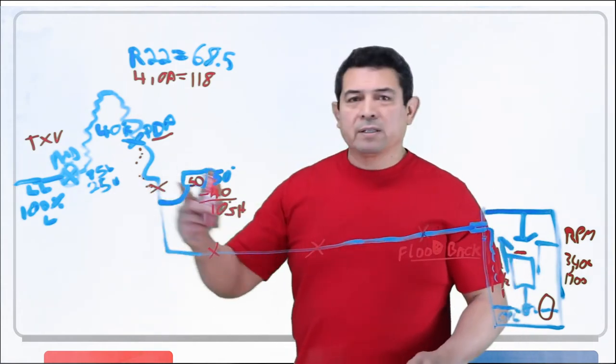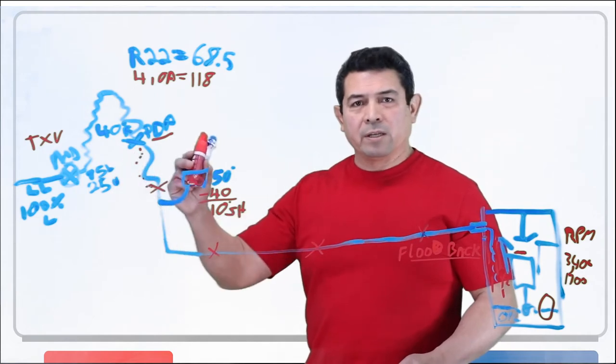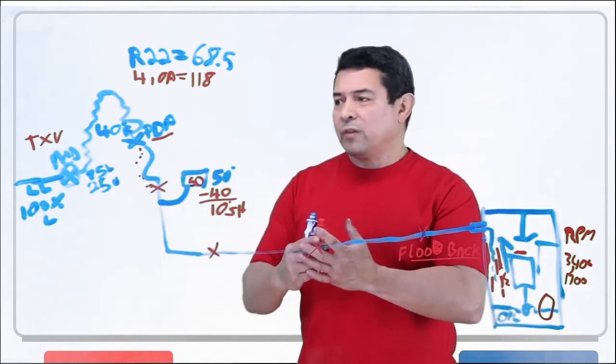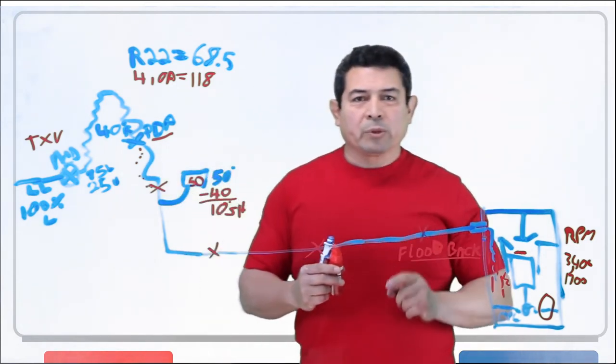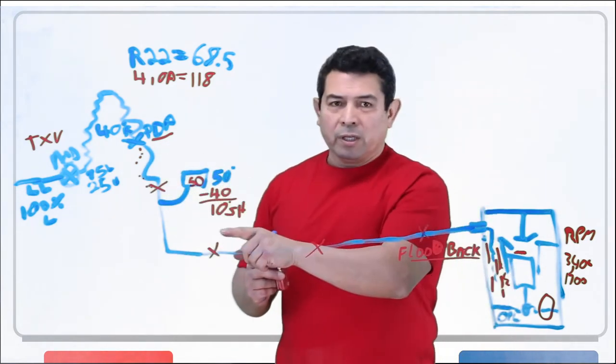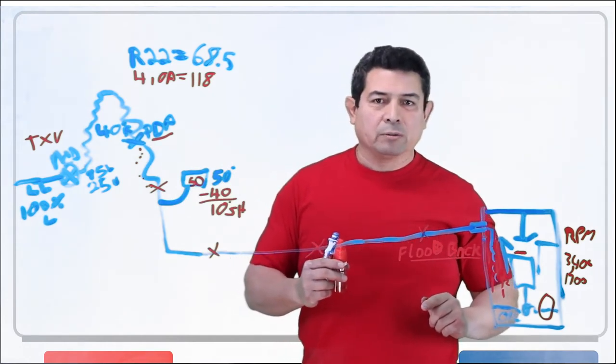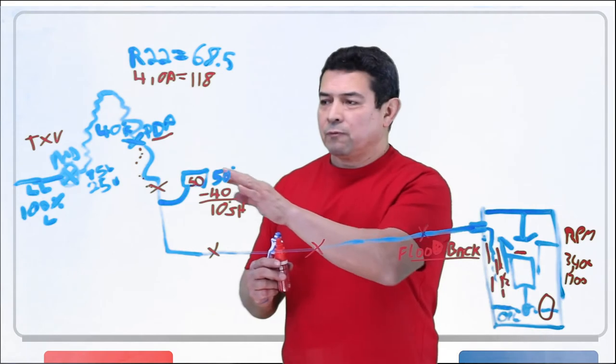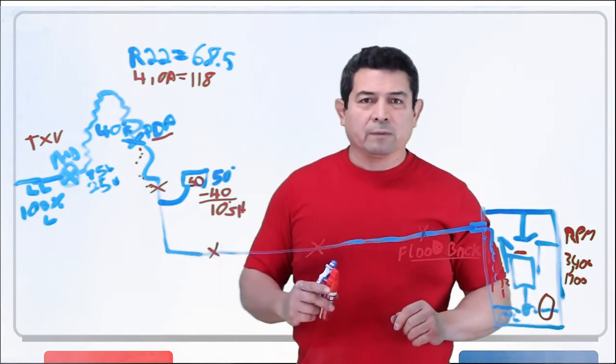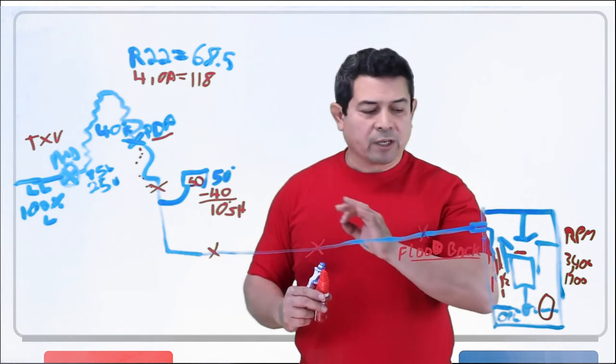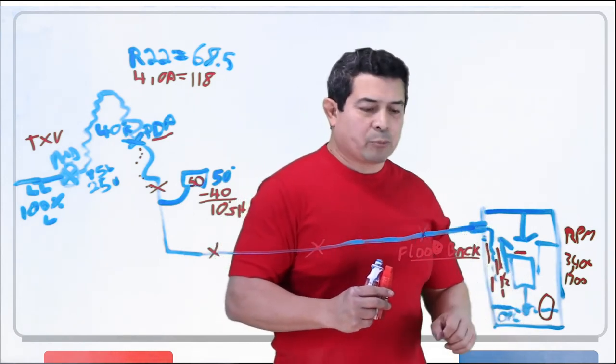If we were to replace the TXV, if we were to replace the metering device here and put one that's not broken, put one that's working properly, then we're going to see that we have the proper superheat. If you have superheat, you're not going to get liquid coming back to the compressor. It's impossible for you to get liquid coming back to the compressor if you have superheat. So it's very important for you to check that. We said flood back is when liquid comes back to the compressor.